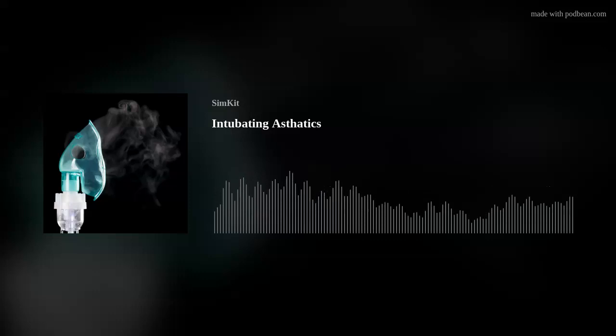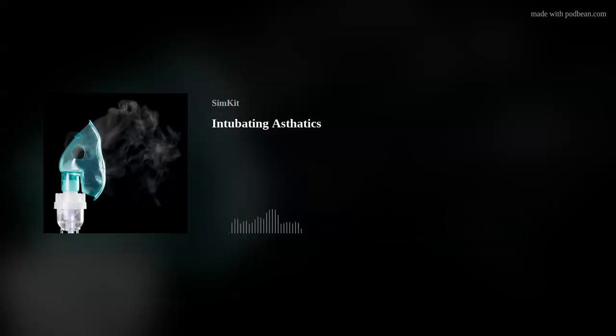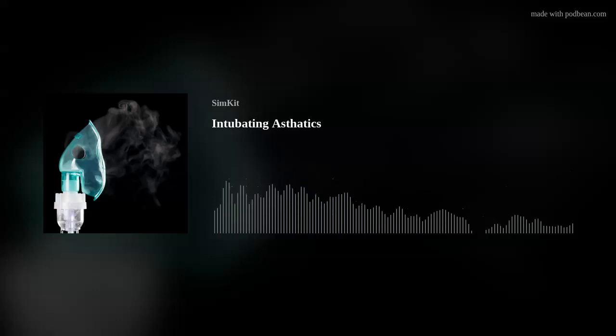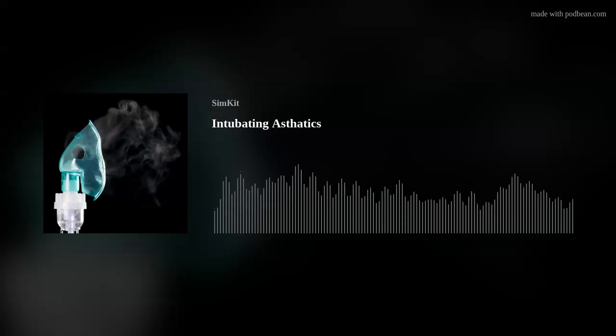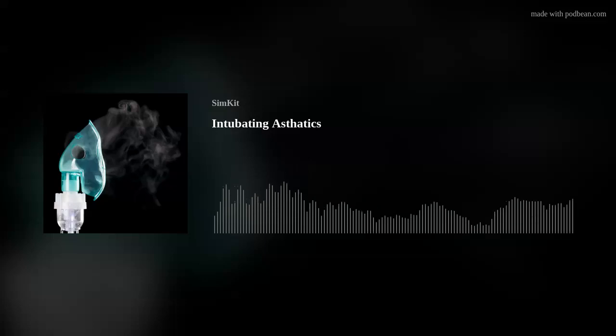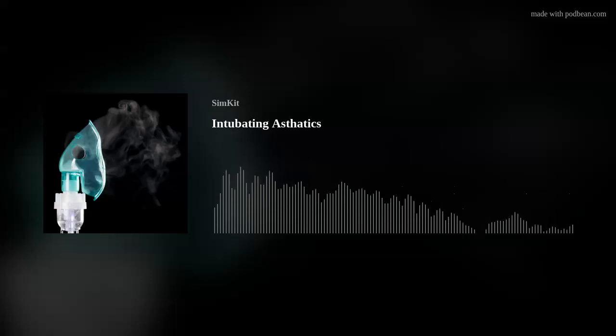That peak pressure alarm on a ventilator is not just a, hey, maybe you want to take a look at it kind of alarm. It's actually not even just an alarm. All of the ventilators that I've ever seen, I've asked all the reps. So we're talking Draeger, Hamilton, Vyaire, and others, all of them. I'm just naming a few off the top of my head, right? Those are some major players in the ventilator arena.